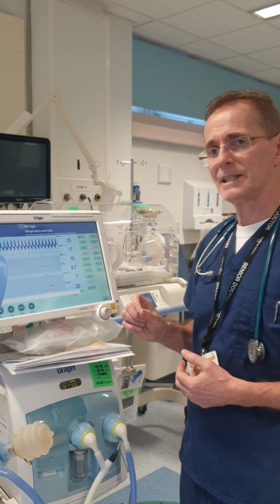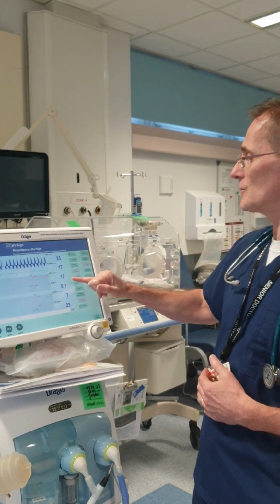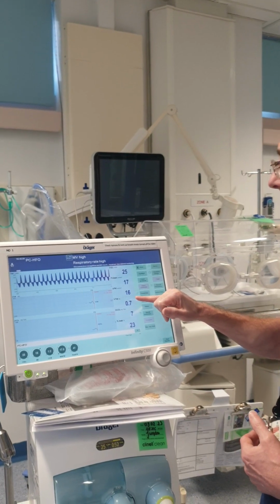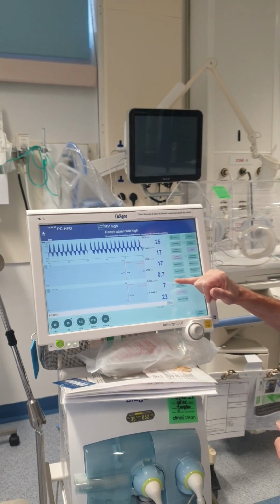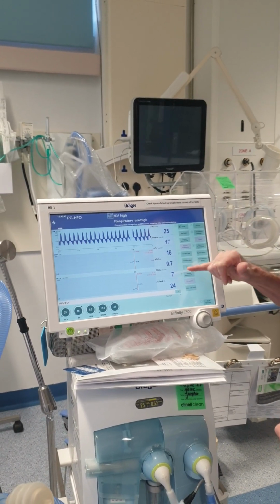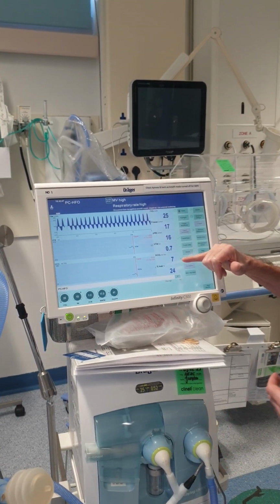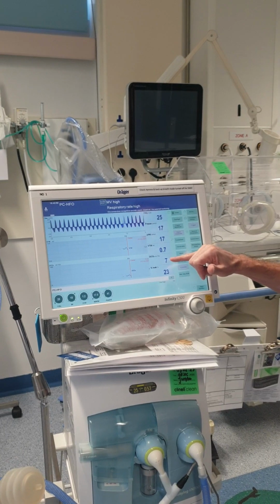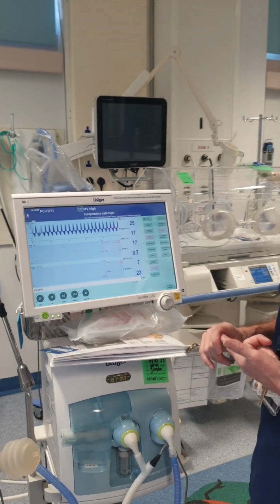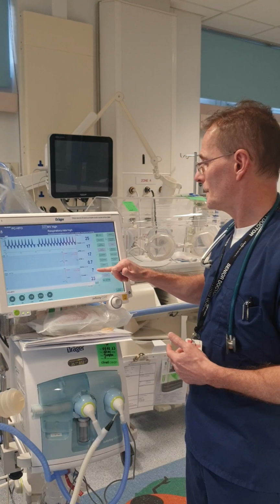The tidal volume in oscillation is about 1 to 2 mils per kilogram. So if you've got a 1 kilogram baby, this machine is telling me 0.7, we're not achieving an adequate tidal volume in this baby. The other thing is, your delta CO2 is a very good indicator and a very good parameter to be aware of. The delta CO2 tells you your effectiveness of CO2 clearance. If that's in single figures, you're not achieving any CO2 clearance. And your delta CO2 is a product of your frequency times your tidal volume squared in oscillation. So it's very low.